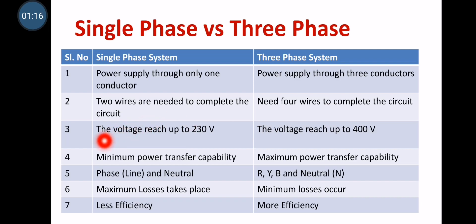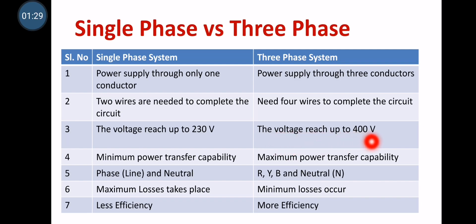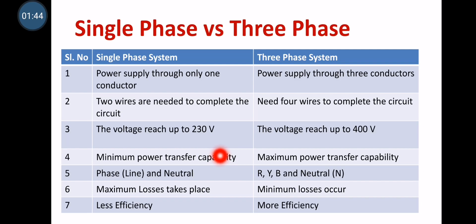Moving on to the third difference. The voltage is reaching up to 230V — the maximum voltage is 230V plus or minus 10%, where that 10% is the tolerance. But in case of three-phase system, the voltage can reach up to 400V. Another difference: the power transfer capability is very limited in single-phase system, so you can't satisfy heavy load requirements. Only light load applications are suitable. If you want to go for heavy load like a three-phase induction motor, we definitely require three-phase system, which ensures maximum power transfer capability.